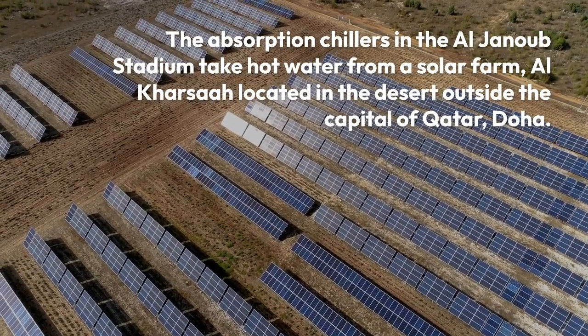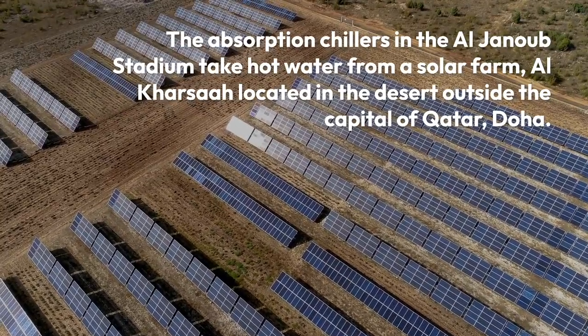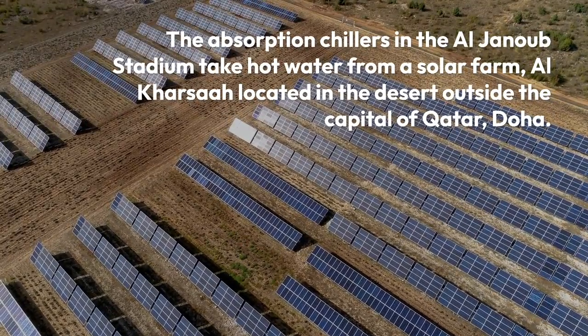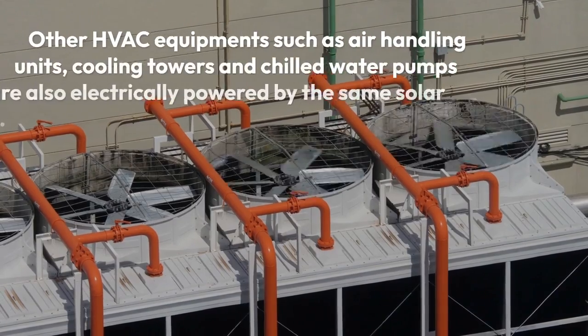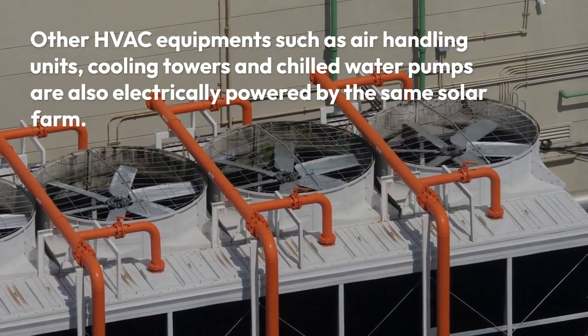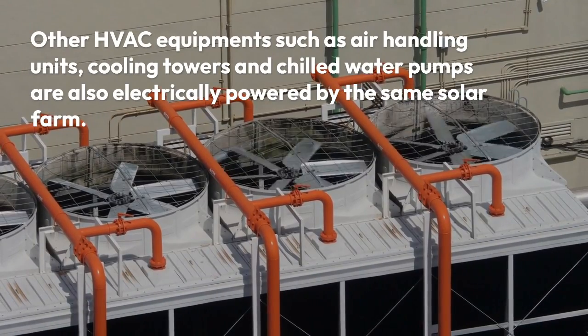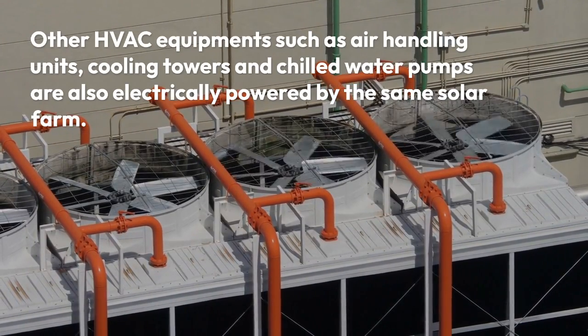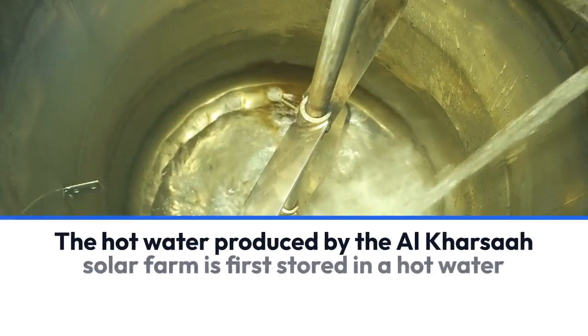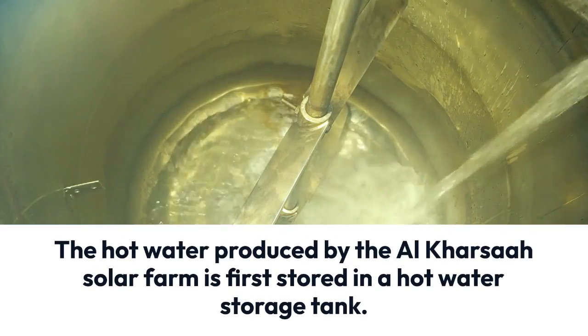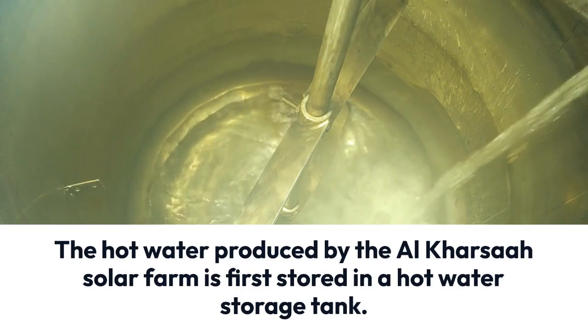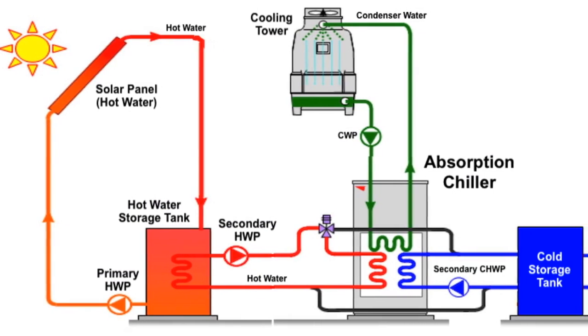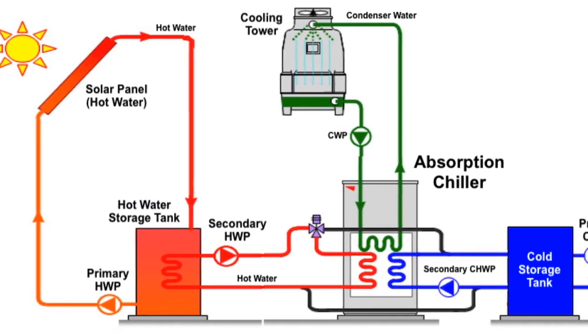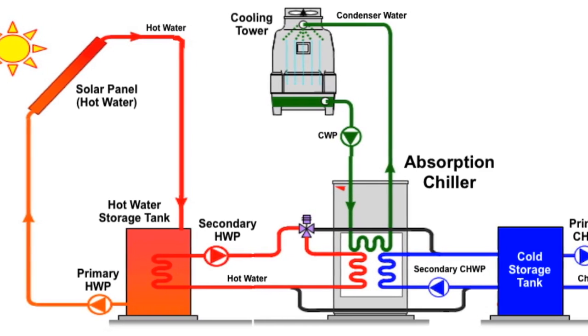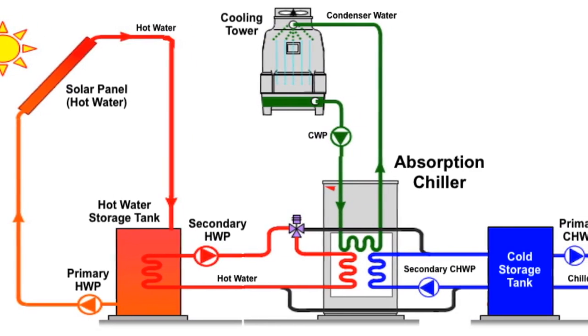The absorption chillers in the Al Janoub Stadium take hot water from a solar farm, Al Kharsaah, located in the desert outside the capital of Qatar, Doha. Other HVAC equipment such as air handling units, cooling towers and chilled water pumps are also electrically powered by the same solar farm. The hot water produced by the Al Kharsaah solar farm is first stored in a hot water storage tank. This is the thermal harvesting loop that circulates hot water between the solar panels and the hot water storage tank to maintain the desired hot water storage temperature.